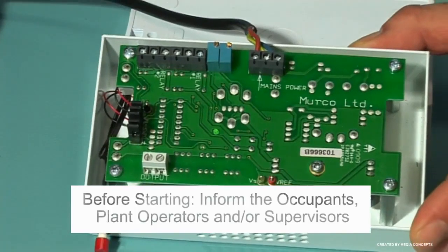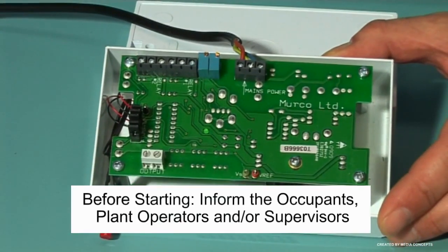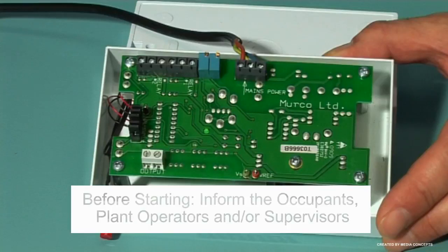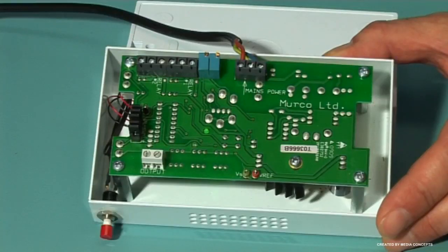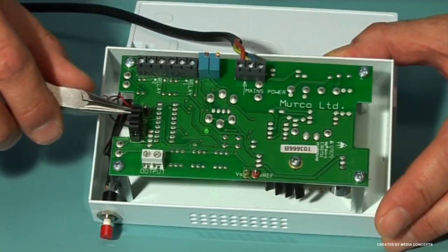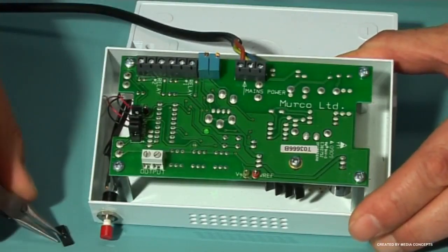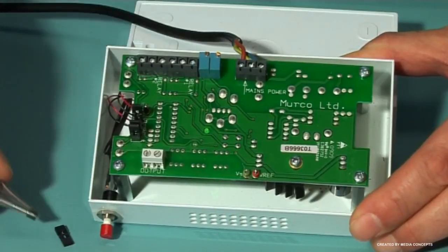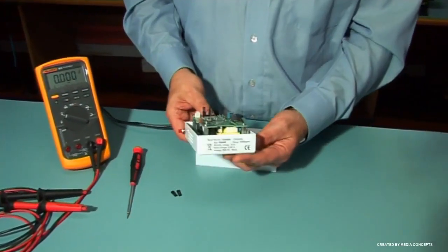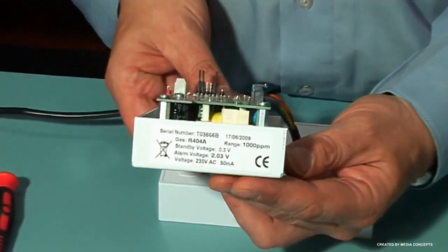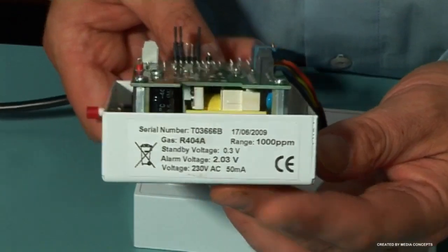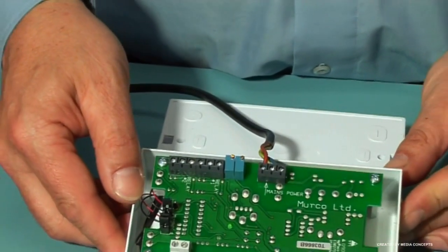Before starting, inform the occupants, plant operators and/or supervisors of the test. Check IAM connections to external equipment and disconnect if required. Deactivate any delays by removing jumpers 1 and 2 on HD1. Before performing your test, the IAM must be powered up overnight. The electrical setup: the rating label on the side of the IAM gives you the standby voltage and alarm voltage factory set points. These values were established during the initial factory calibration of the unit.